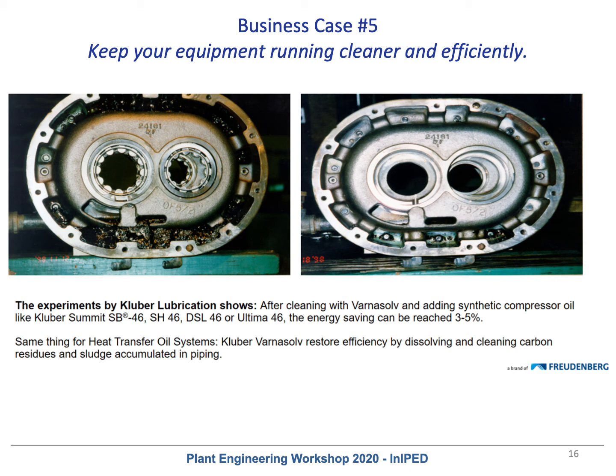lubricant. So, an experiment by Kluber Lubrication shows that on a compressor that was running with mineral oil and was full of varnish and sludge, we proved that after cleaning with Varnasolv and, upon fill-up, adding a synthetic Klubersynth compressor oil like our SB, SH, DSL, or Ultima series, the energy saving can reach between 3 and 5% by cleaning the equipment first with Kluber Varnasolv and then switching over to a synthetic oil. Same thing with heat transfer oil systems.